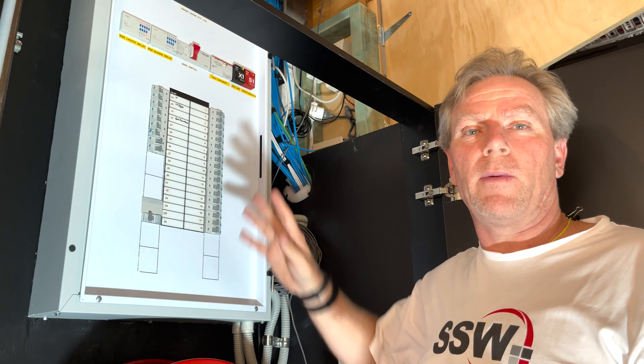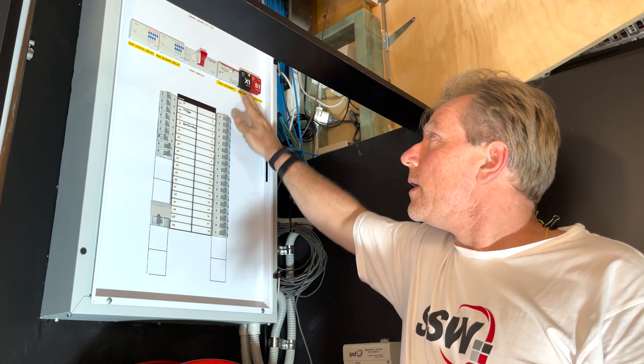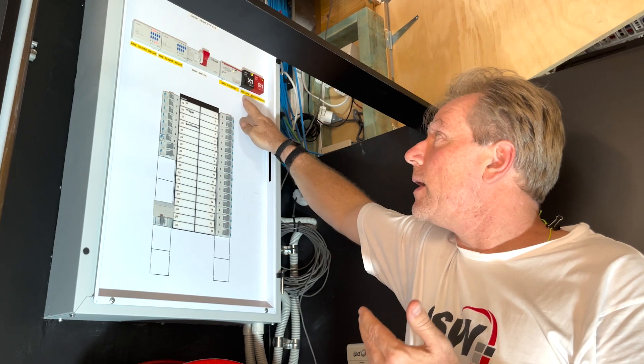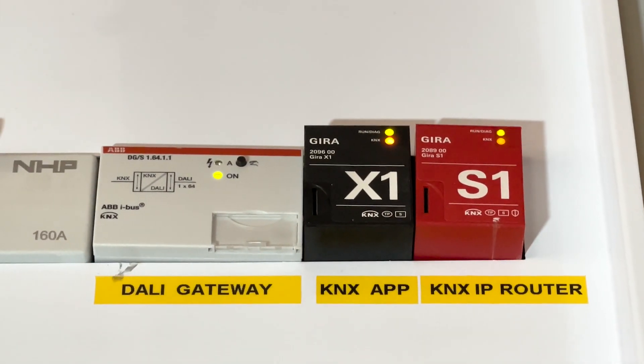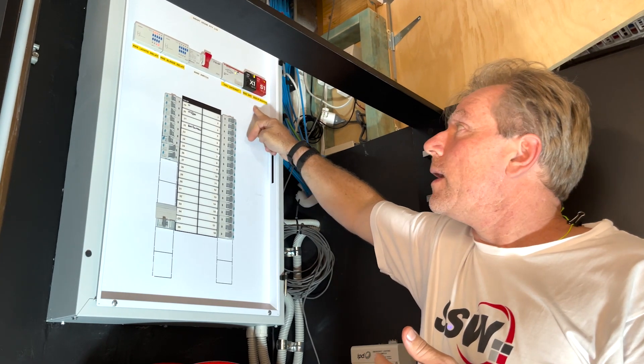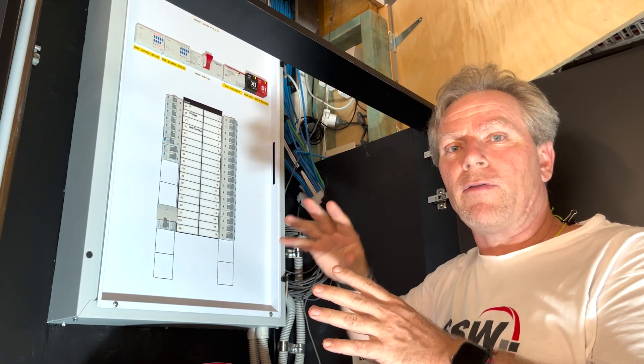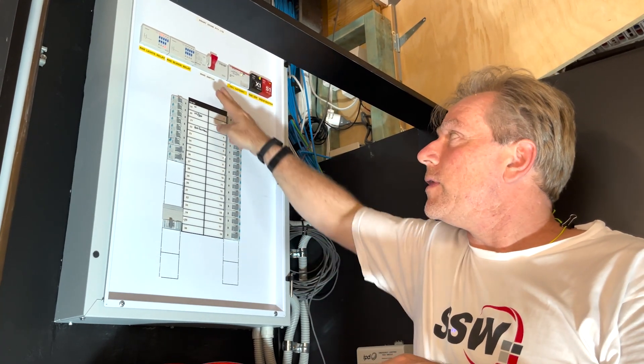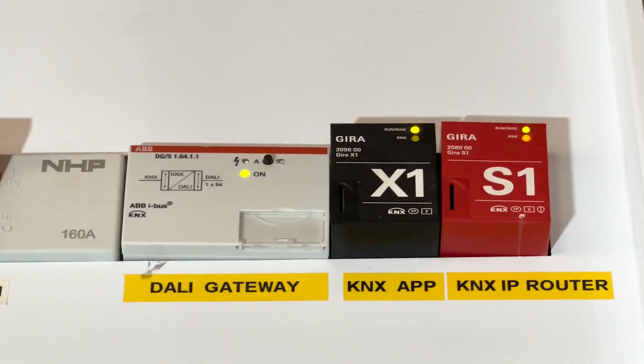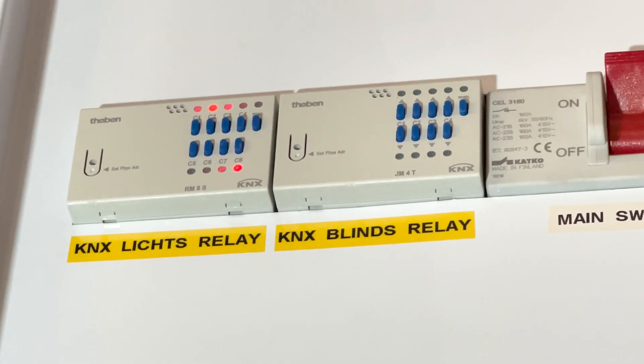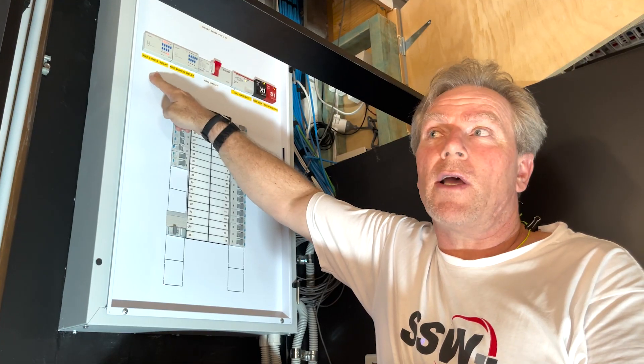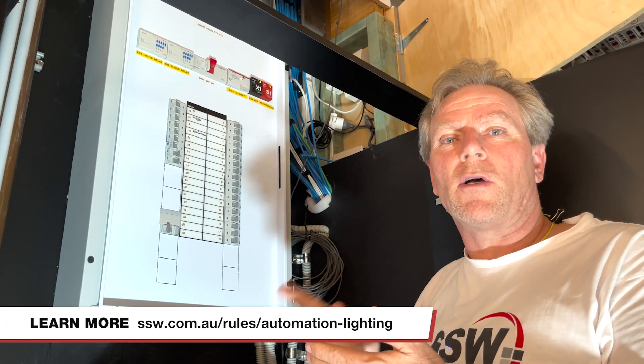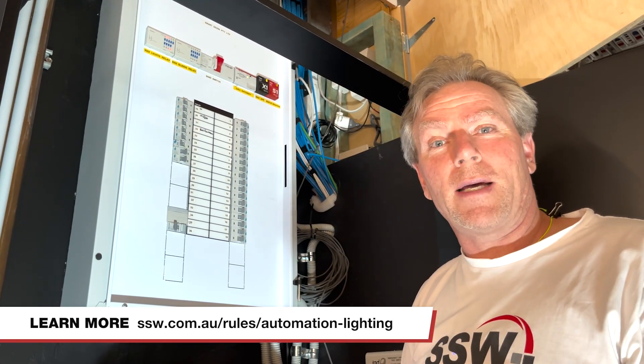So here we have the hardware. This is the distribution board. This is the main brains. This is what talks to the app. It's the Gira X one. And if you want remote access, you need this IP router. This is the DALI gateway, which allows every single light to be turned on or off. And this turns all power on and off. Now, we also have our blinds that go up and down via the app and automatically. And this is only because we have a stage where we want to be able to remotely turn lights on and off stage lights. So that's all the hardware.